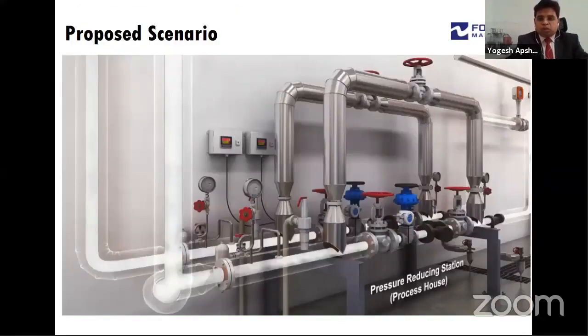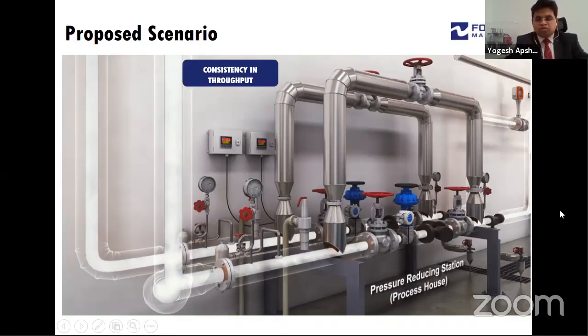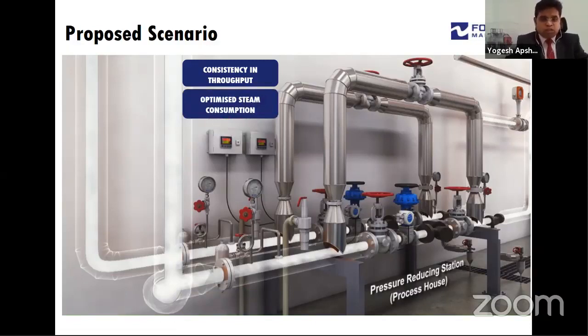So this is the scenario proposed by us. This is the pressure reduction station, which consists of the inlet valve, outlet valve, pressure reducing valve, pressure reducing control valve, then the bypass valve, the moisture separator, and the strainer. What it maintains is consistency in the throughput of the WFI and pure steam process. Then it optimizes steam consumption, so that steam consumption is ideal. This is what we recommend in the clean rooms.